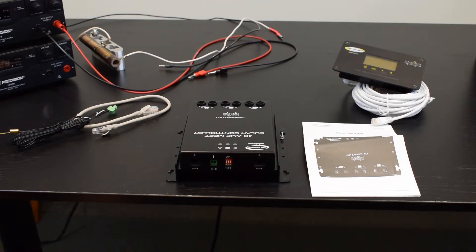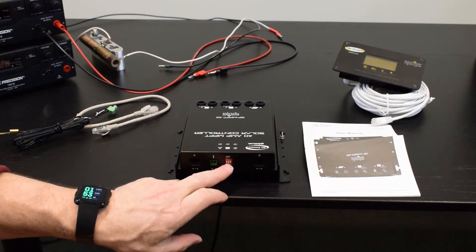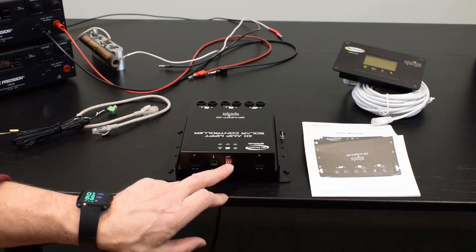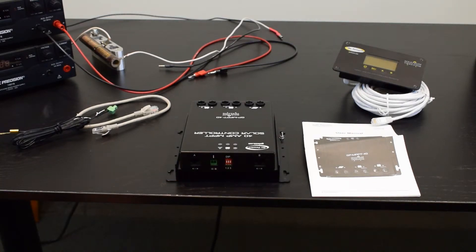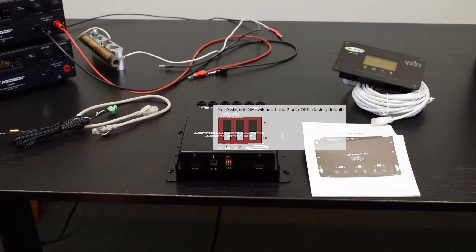The profile is determined by the first two dip switches on the unit itself. So if they're both down in that position as they're shown in the image here, that would be the AGM profile.